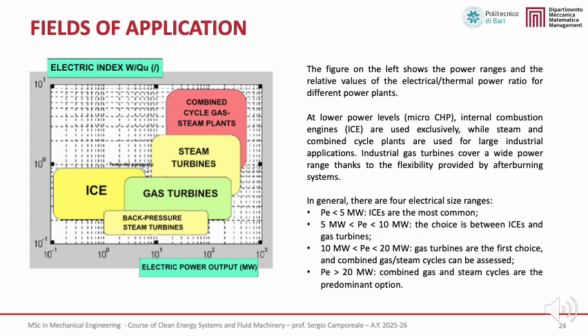Between 10 and 20 megawatts, gas turbines are usually the first option, while combined cycles may also be assessed. Above 20 megawatts, combined gas-steam cycles represent the predominant solution. Overall, this slide highlights that the choice of cogeneration technology is strongly scale-dependent and must be interpreted carefully, taking into account both the logarithmic nature of the diagram and the required balance between electrical and thermal energy outputs.